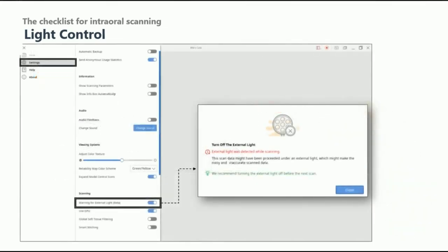The first one is external light. Exposure to bright lighting can affect the precision of the scan data. Avoid patient chair light or any lighting around you. If you enable Warning for External Light in Medit Scan for Clinics settings, the system will send a notification message when an external light is detected.